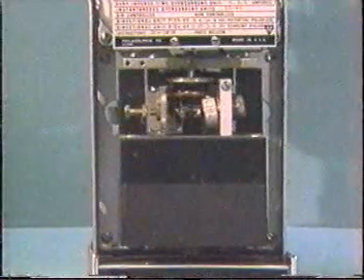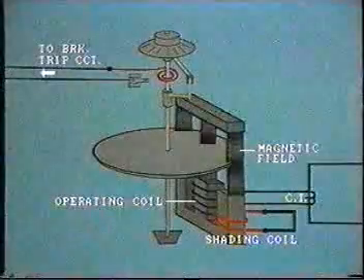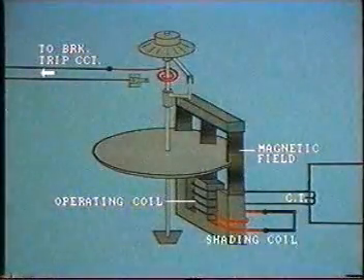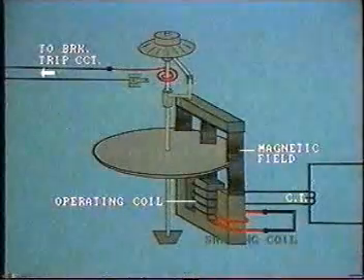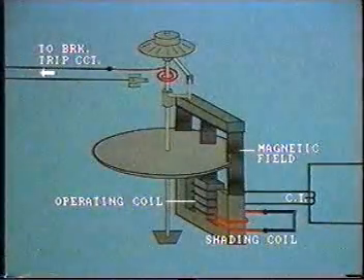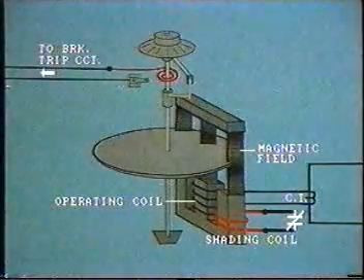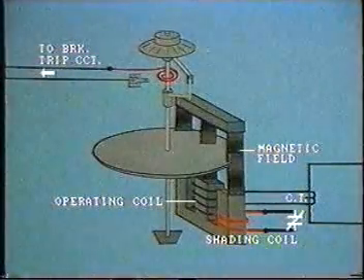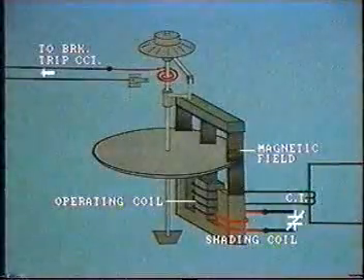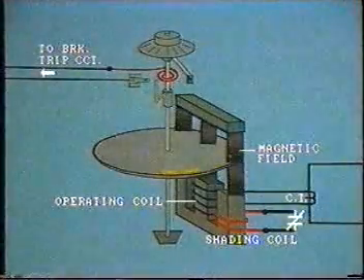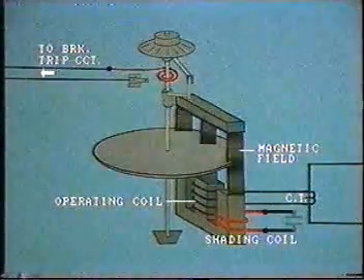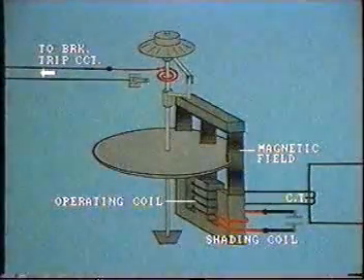The directional element controls tripping by superimposing its operation on that of the overcurrent relay. The time overcurrent relay is fitted with a shorted shading coil on one leg of the electromagnet to provide the driving force. The shorting circuit is fitted with a contact which is operated by the directional element. When current flow is in the tripping direction, this contact remains closed and the overcurrent relay can operate. However, if current flow reverses, then the directional element opens the contact, so preventing operation of the time overcurrent relay.